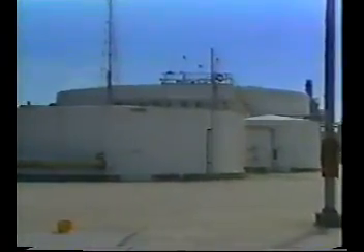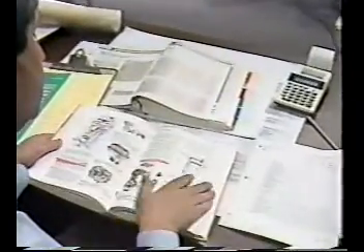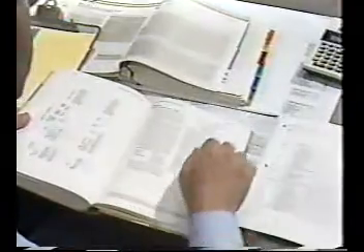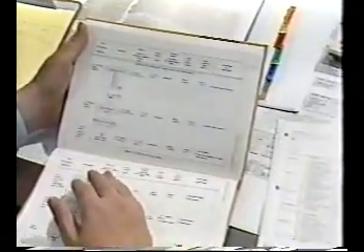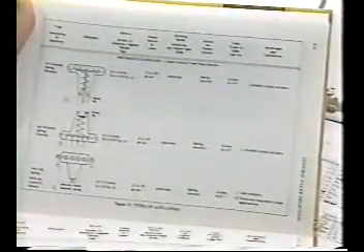Another factor that will influence the decision is whether pneumatic, hydraulic, or electrical power is available. Obviously, the use of an actuator type that does not have a readily available power source may add considerable expense to the installation. After you've identified the power medium available, details of the various actuator styles in that category must be examined. Compare this information to the needs listed on your data sheet to determine the actuator type that will do the job. For example, suppose the initial choice is a pneumatic actuator.